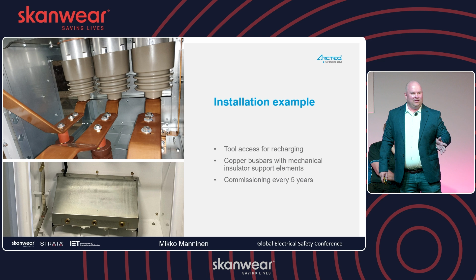So it kind of works like a car airbag. When you have a flash, for example, there, this arc quenching device closes close to the main breaker and absorbs the arc flash energy into the arc quenching device. Meanwhile, simultaneously, the breaker is being tripped. And similar for the medium voltage or high voltage, up to 24 kilovolts. And one installation example, directly bolted to the bus bars. Hopefully I didn't break it.